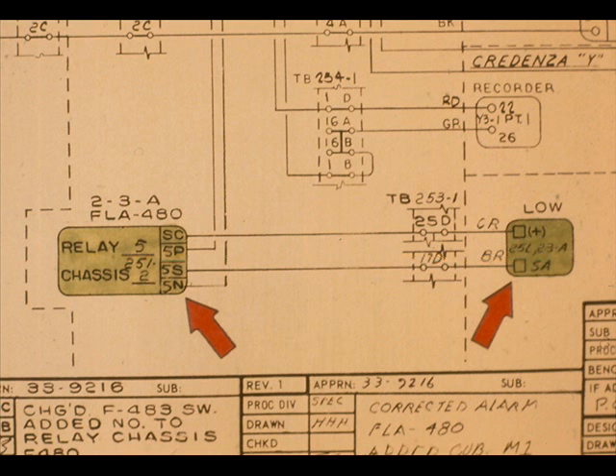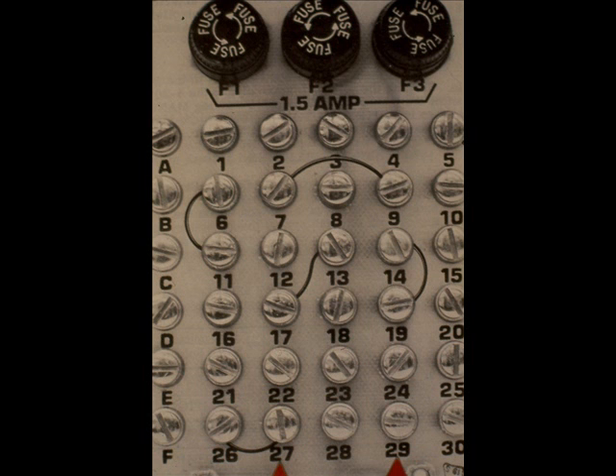Notice that this loop also contains a low flow alarm. This is the back of the Veritrac controller. These numbers correspond to the loop diagram controller terminal numbers. The controller receives 24 volts DC on terminals 29 and 27 of the controller.